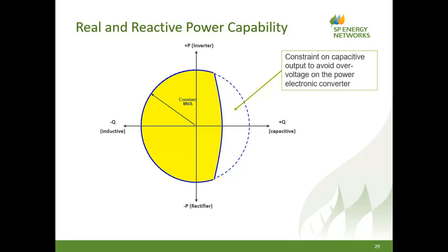As we try to export capacitive reactive power, we have to increase the generated voltage, the magnitude of the generated voltage, and that puts voltage stress on the IGBT devices. So there is a limitation of voltage on the capacitive output, which limits our scope of generating capacitive reactive power. On the inductive side, we have to decrease the generated voltage, and decreasing the voltage never hurt anybody. So we have more scope on the inductive side to absorb reactive power.